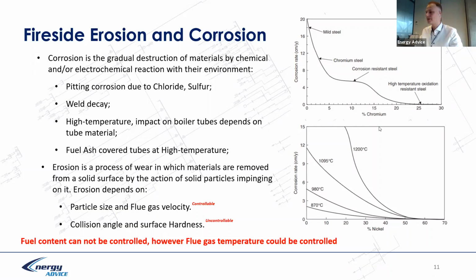and why it's important: I put here a couple of examples, which are probably not the right examples for the right case, but they represent the idea that the corrosion rate depends on the content of a steel, chromium and nickel, yes, the composition of a steel. But if you look at the corrosion rate in centimeters per year, it highly depends on, for example, the nickel content. It increases exponentially with increasing temperature. So we have a boiler design temperature and we have the real temperature, and by controlling the temperature, we can control the corrosion rate.